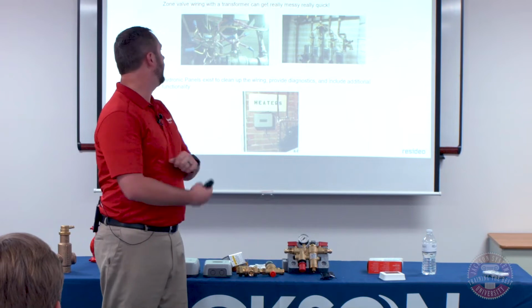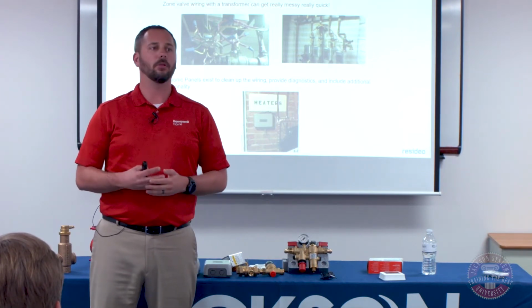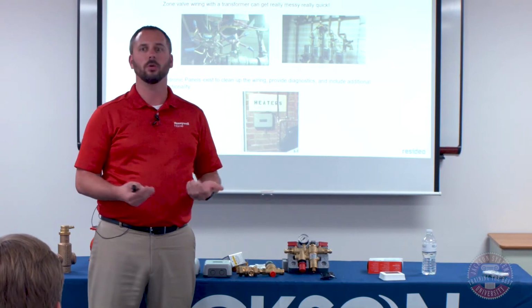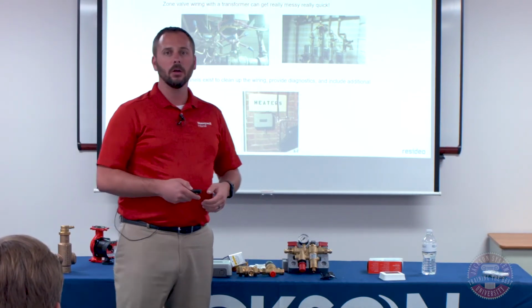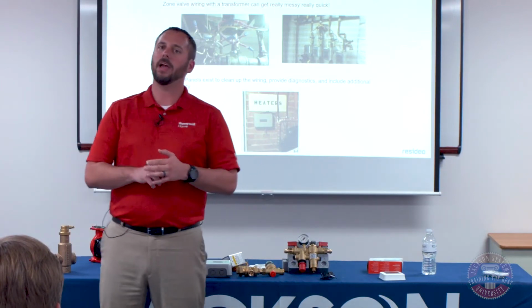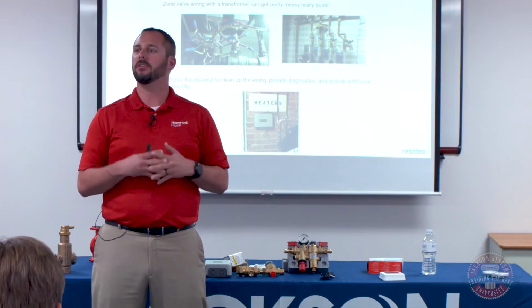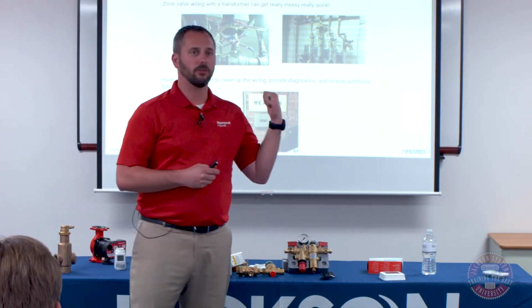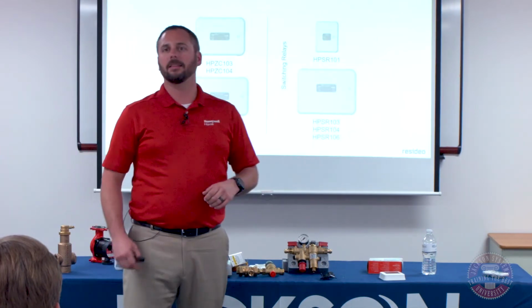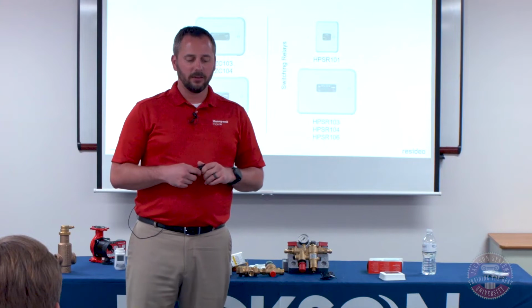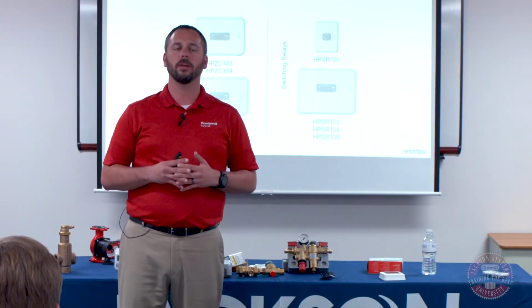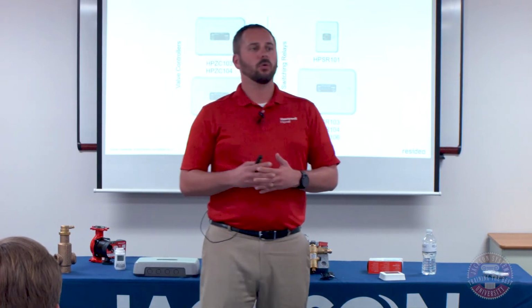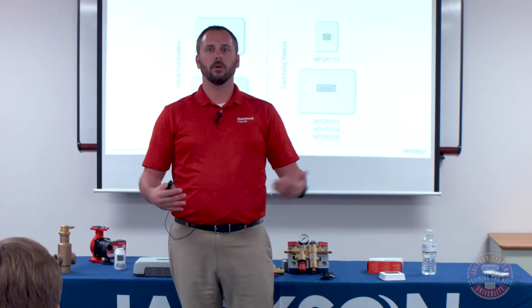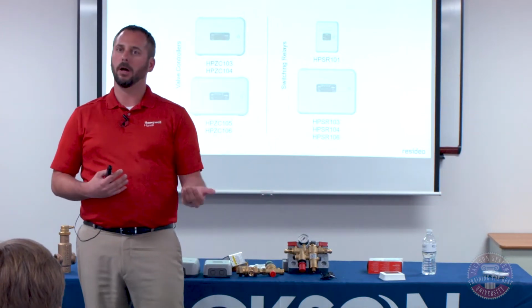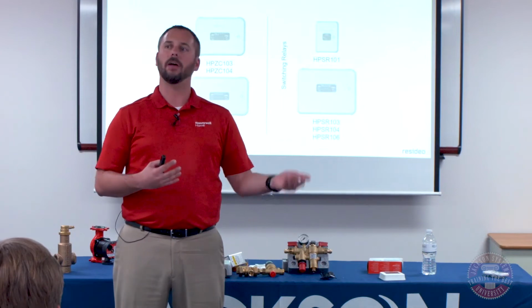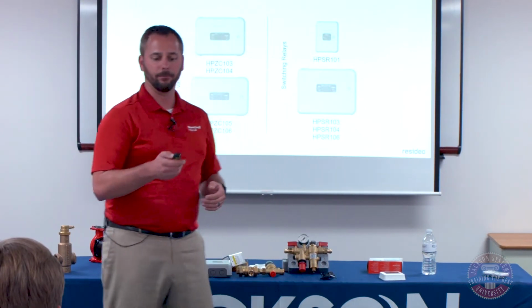It can look good. It works just fine, but the problem becomes, what do you do down the road when you need to go back to the job site if there's any kind of an issue, if you have to access it to service it? It becomes a giant pain. So what we've done is we've finally created, because we've had high-level controls for a while, a very simple relay control. It could be with zone valves or pumps. We've got these hydronic panels now. You've probably seen some stuff very similar to these in the past, but think of it as the landing point between the zone valves or pumps and the thermostats. It's going to take the call for heat from the thermostat, tell either the pump or zone valve to turn on, depending on how you're doing it, zone valving or pumping. And then it's also going to tell the boiler to come on.